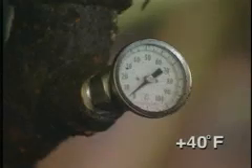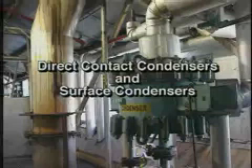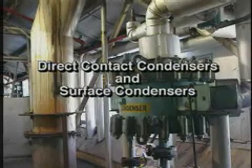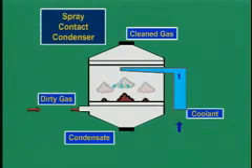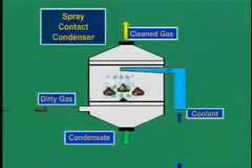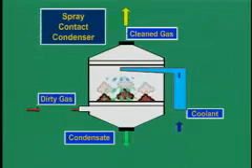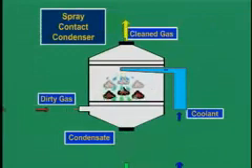Conventional systems are relatively simple devices that usually use air or water to reduce the gas stream temperature to as low as about 40 degrees Fahrenheit. Temperatures as low as 0 degrees Fahrenheit can be achieved using brine coolants. There are two categories of conventional systems: direct contact condensers and surface condensers. Direct contact condensers are essentially wet scrubbing equipment like spray towers or tray towers that directly contact the gas stream with a chilled liquid, usually water.